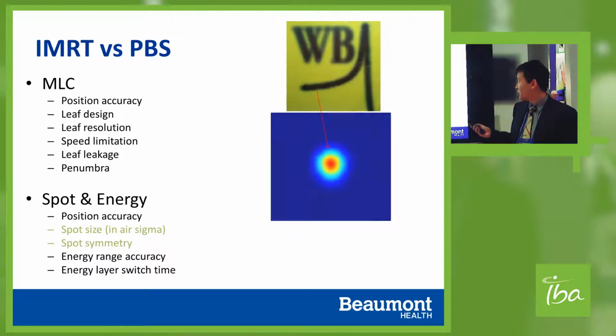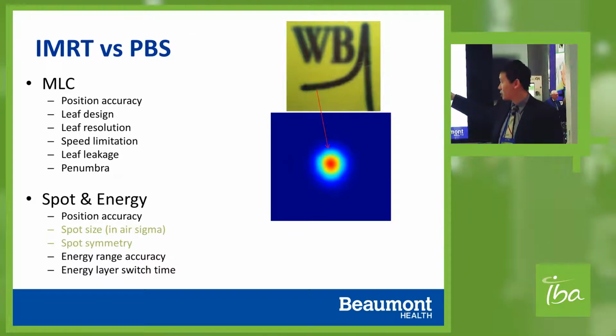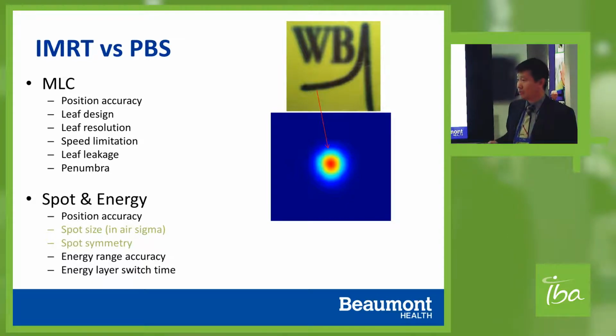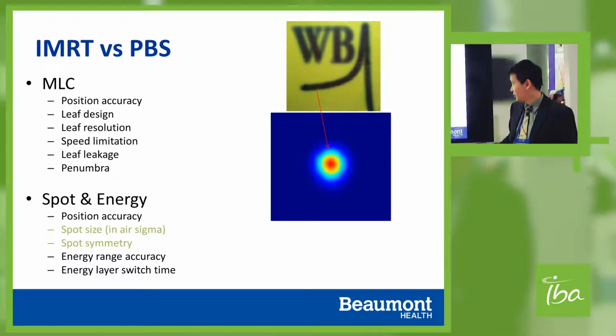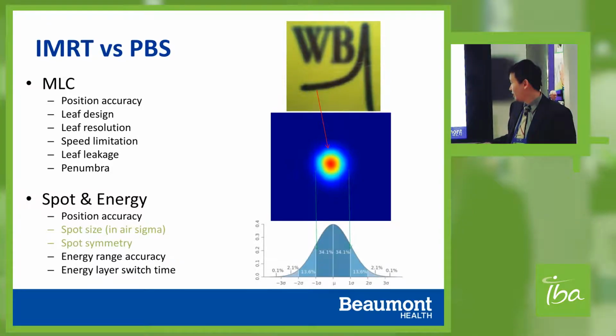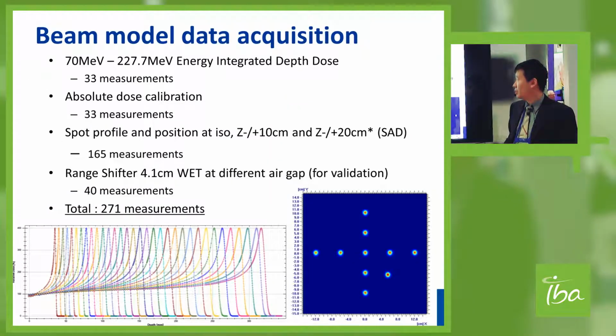So in terms of measurement, you want to really have a real characteristic of a circle shape, a symmetric shape of your spot, to make your life easier, especially for the physicist, to make sure the beam model is not a challenge anymore. So in terms of beam data collection for RayStation, we have 271 measurements to submit to the RayStation.